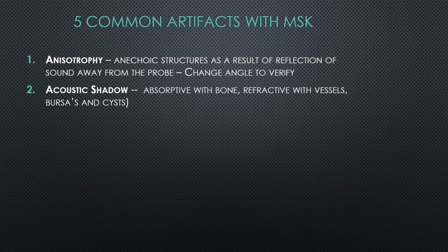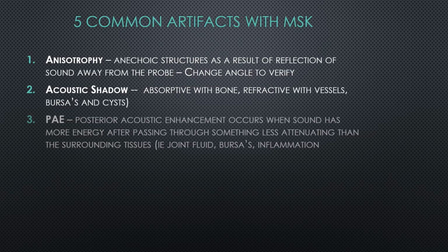Acoustic shadow, you've been introduced to those as well. So that's really 3 types of shadows that we'll talk about, but we're talking about bones and something that absorbs all the sound. That's going to be an absorptive shadow. You can have a refractive shadow, which is very similar to what you see with light, where it bends the sound around the edge, so there's nothing else coming back from it. So that is sometimes known as an edge artifact. And then, of course, you can have things that will eventually attenuate structures all the way down, and you end up with a scatter shadow, which happens with air.